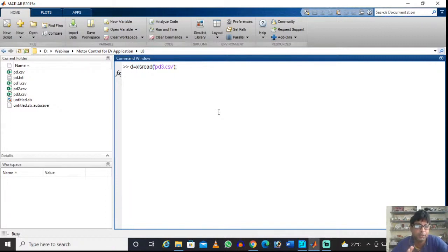But the thing I am telling you, when you are working, or people who are working in industry, you can follow the same method and you will get a very good result, because this is my regular practice to tune the system. First, I will make the system open loop using a data logger. Because the occurrence of the transient I know, since that will be given by the designer of the system. So I will ask what your transient time is. I will take the sampling time at minimum 1/1000 or 1/10,000, and I will capture the data.